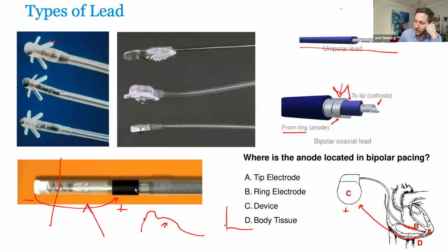So if you look over and your paced signal, you're still capturing, but it's very narrow versus maybe a wider signal here. That could mean that you don't have good tissue contact. In this case, he also mentioned negative. So if you see negative injury current from baseline, that's usually not ideal. You can be tricked depending on how the lead is sitting against the myocardium, but in general, that just means that the electrical impulse is moving away from the tip electrode.